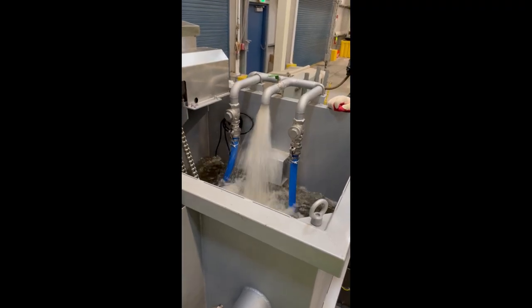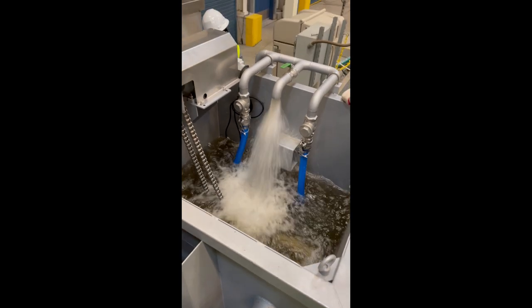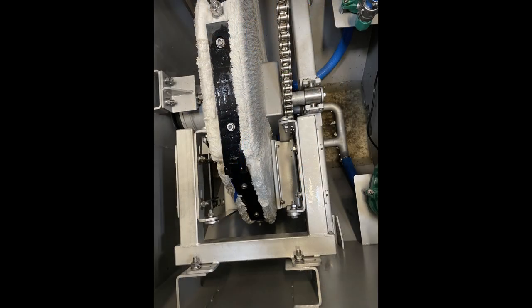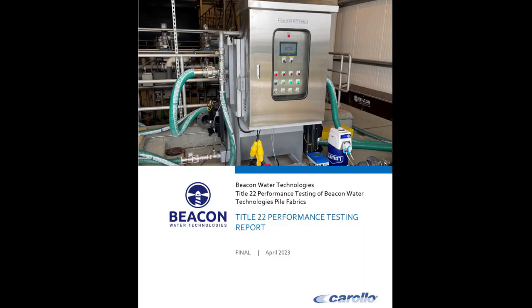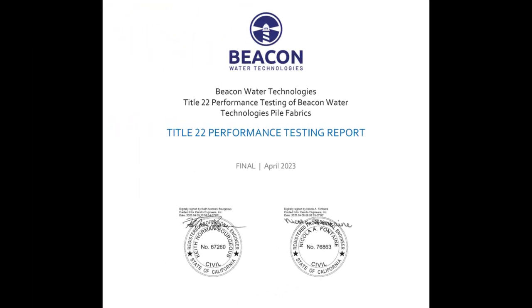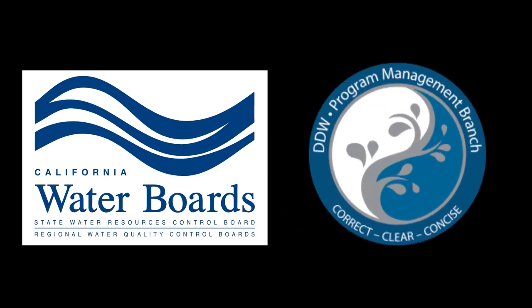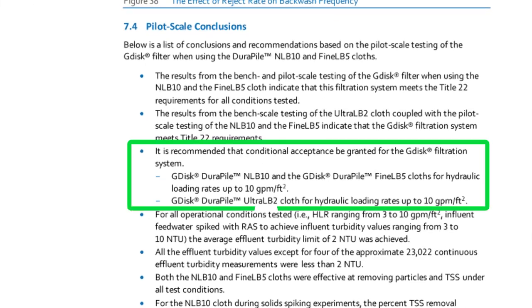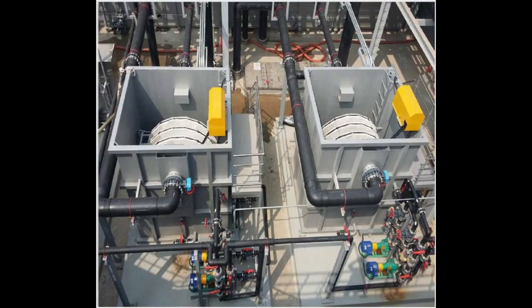Following excellent results from both bench and pilot scale testing of the Beacon G-disc filtration system with three different pile cloth medias, Carollo Engineers has submitted its Title 22 performance testing report final April 2023 to the State of California Division of Drinking Water, or DDW. This document requests conditional acceptance for the Beacon G-disc system with its 10, 5, and 2 micron filtration rated Durapile cloths for use in tertiary recycled water applications.